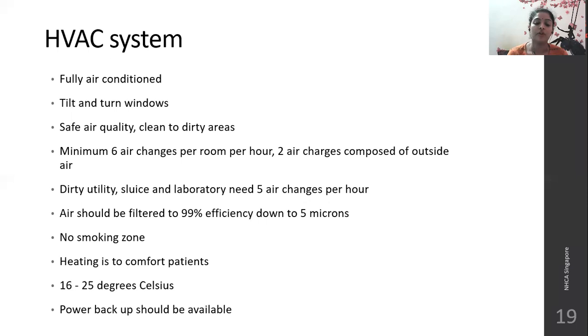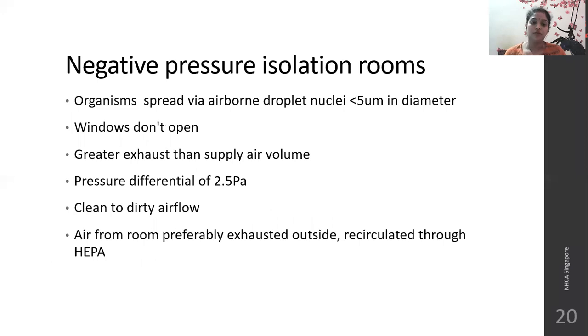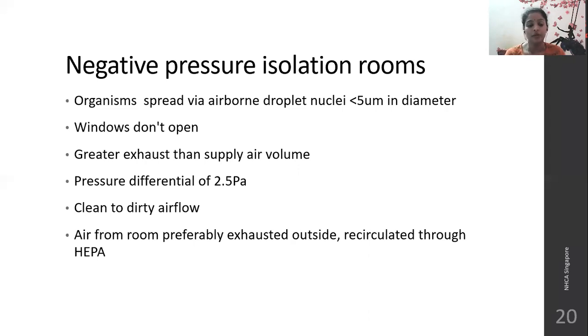In the dirty utility, sluice area, and laboratory area, 5 air changes per hour is adequate. Air filters should have 99% efficacy down to 5 microns. It should be a no smoking zone. Heating is to comfort the patient only, not to control temperature. 16 to 25 degrees Celsius is the ideal temperature for an ICU. Power backup system should be available. For negative pressure isolation rooms, organisms that spread by airborne or droplet nuclei should be placed here. Windows should not be open; the exhaust fan output is greater than the air supply, with a pressure differential of 2.5 PA. Air movement is from clean to dirty, and air can be recirculated through HEPA filtration.